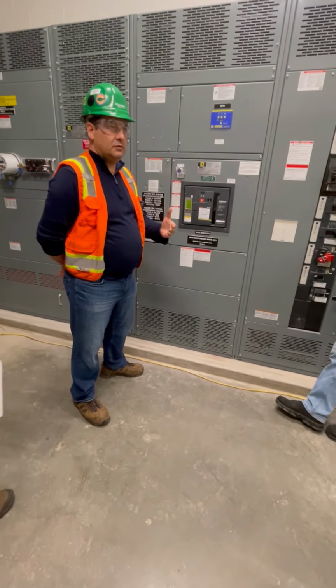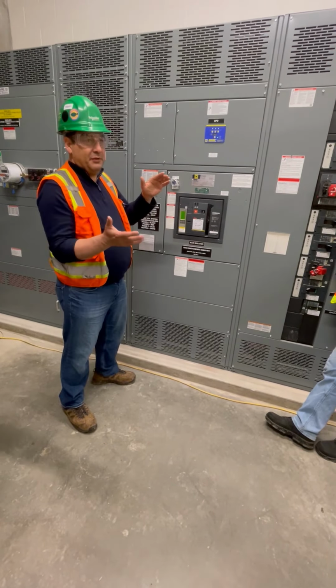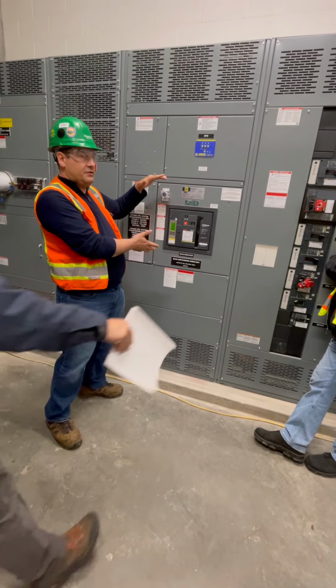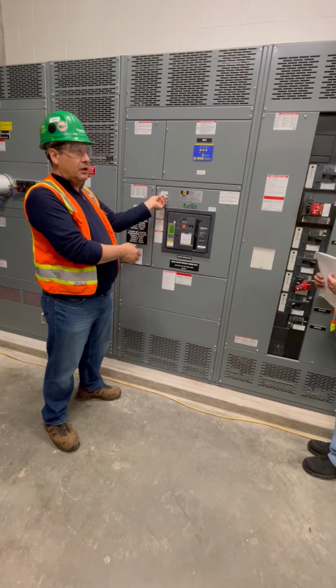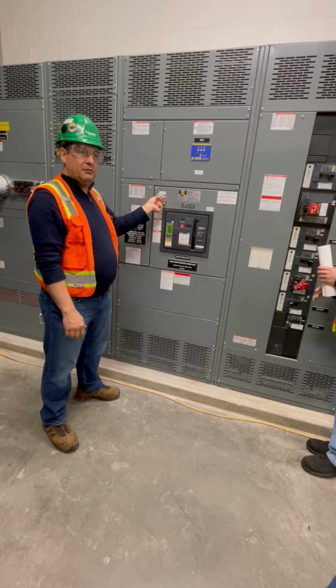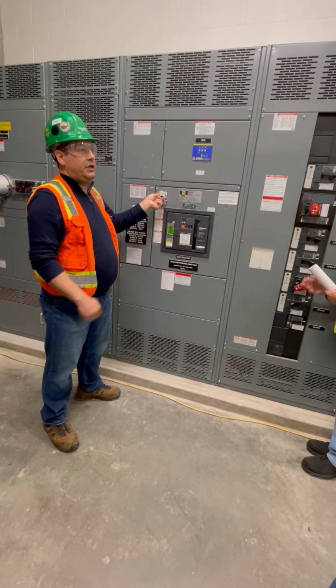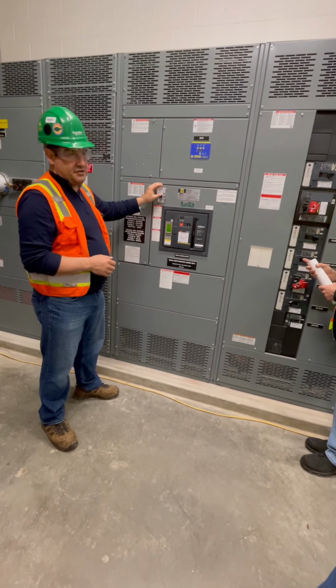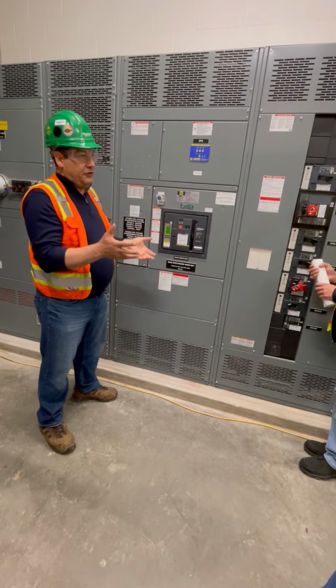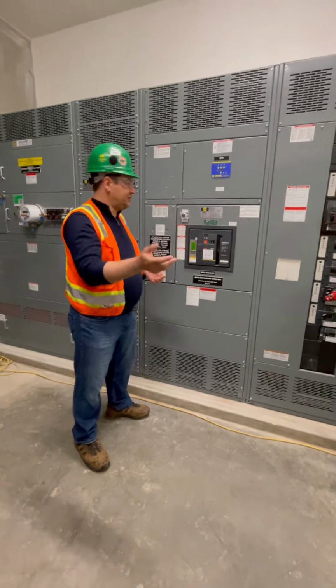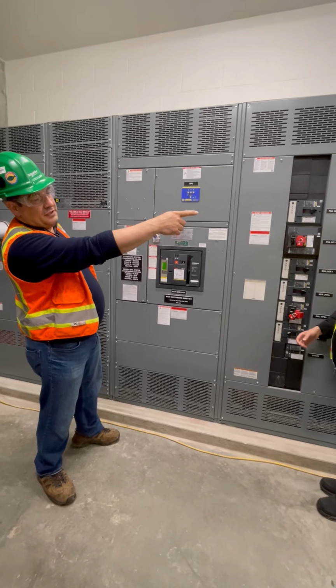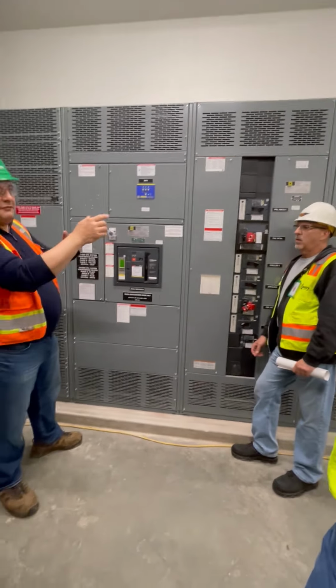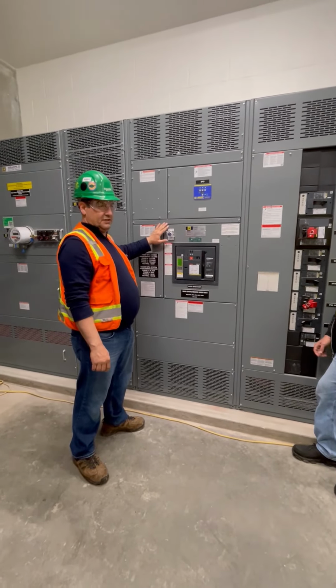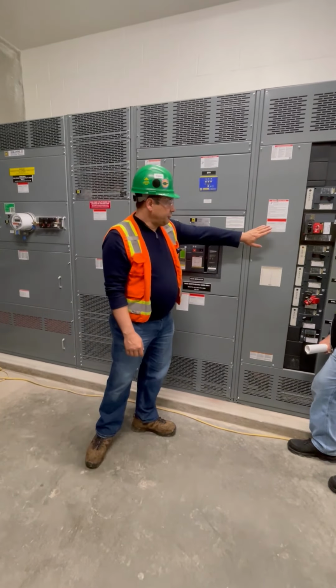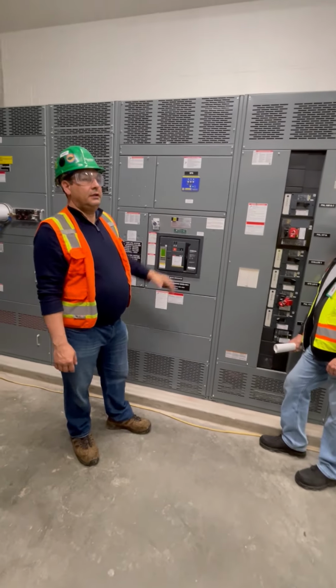And in the study, there should be a table specific to this, so you'll have a couple of tables. One is the arc flash based on the normal operating procedures. But there's another table with a new arc flash calculation when you operate the equipment with this on. But again, this is only to be used if needed; off is the intention of normal operation mode. Now, if you have electricians or yourselves who need to reference a table, if you put this in the on position, you have to reference the table for the on position. If not, you reference the table for the normal, off position. It also changes things, obviously not on this breaker, but downstream. It affects everything downstream.